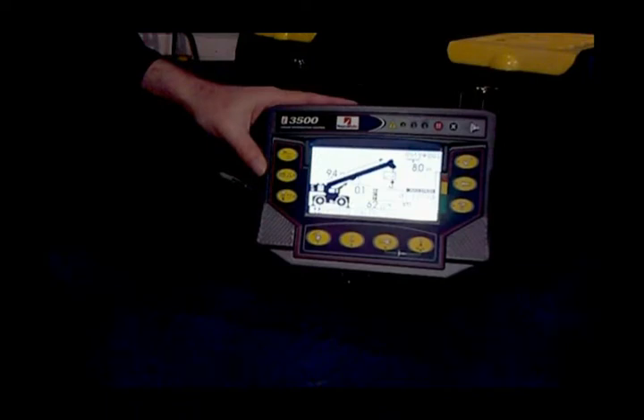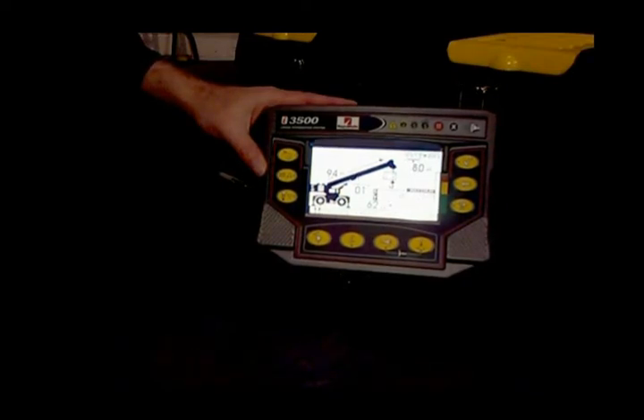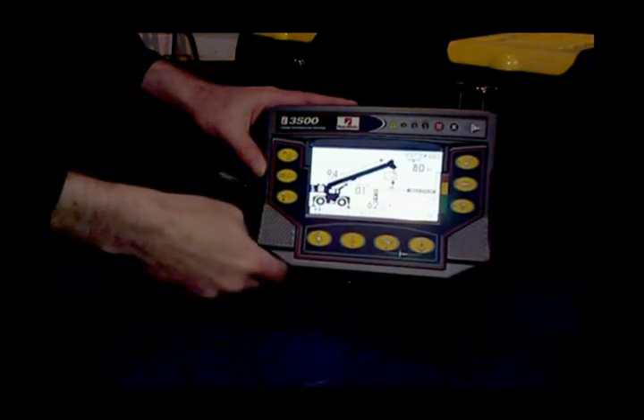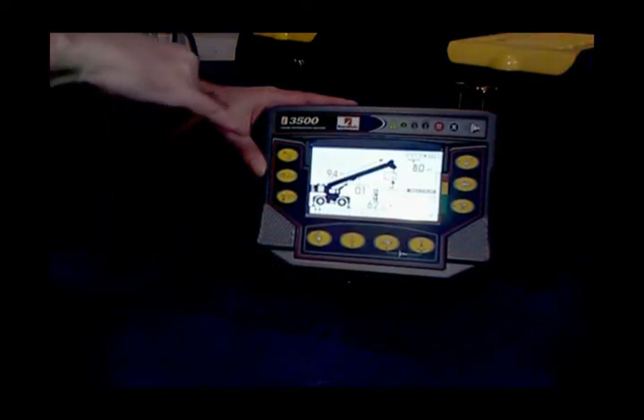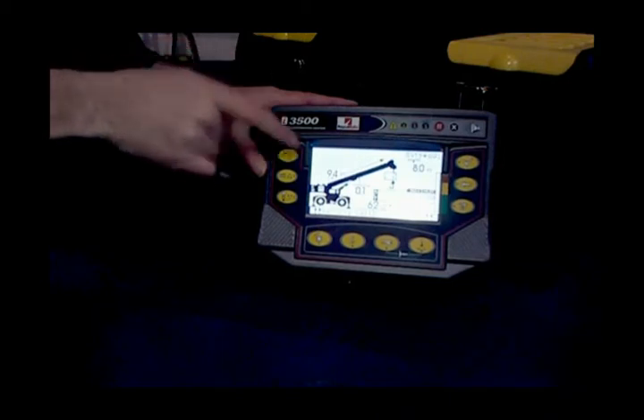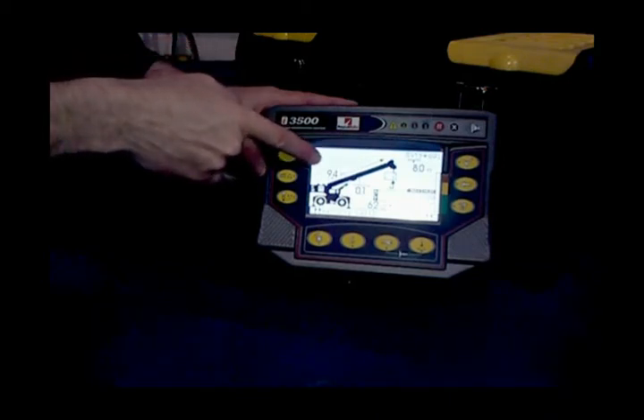So after you've gone ahead and you've done your zeroing and you've spanned by fully extending the boom and inserting the value that we spanned the boom by, what you're going to do is come back and you're going to fully retract your boom and take a look at it on the main screen. Take a look at this value here, which is your boom length. Make sure that your boom length is reading accurate.